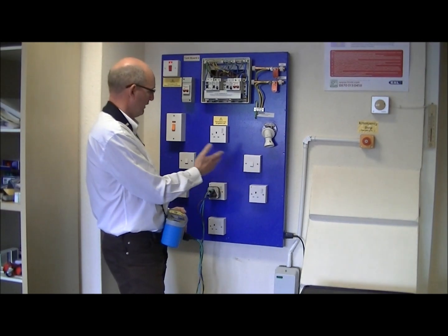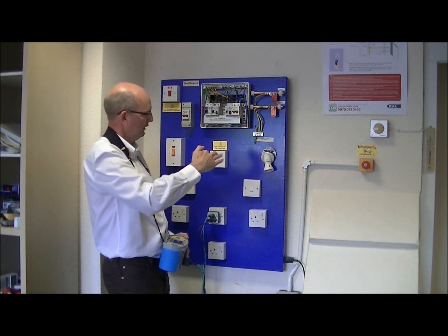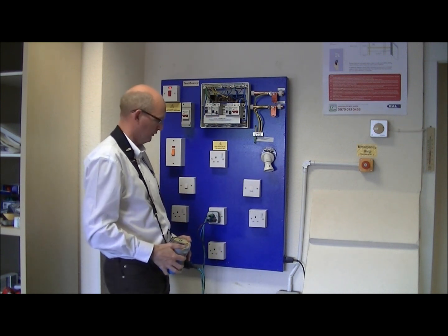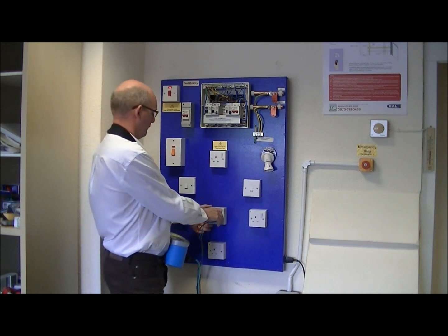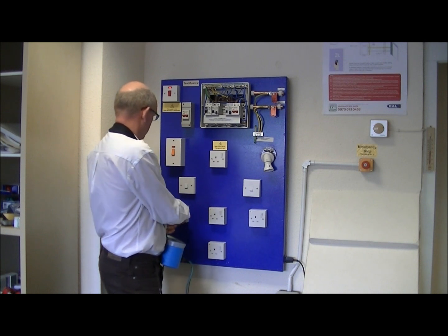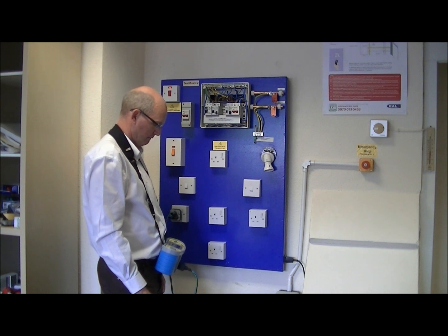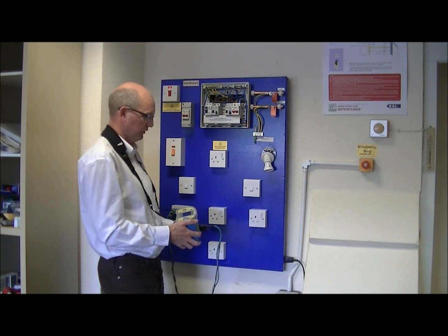And in theory, as we go around the ring and we get further away from the consumer unit, the value should increase. As we come back around the ring nearer to the consumer unit, the value should start to decrease. So the furthest point, or the highest reading, will be the furthest point on the ring. So we continue those tests. So we're nearly done there. It takes a bit of a while because the meter's on a less sensitive setting, so we don't trip the RCD.